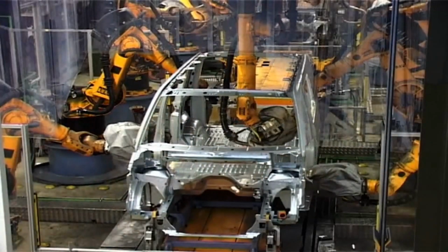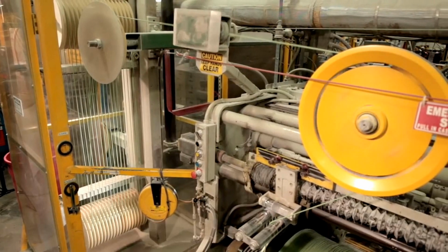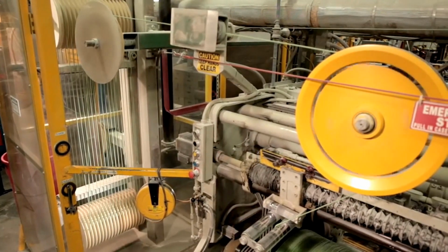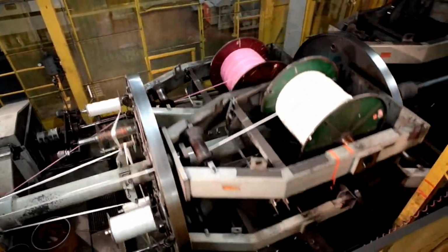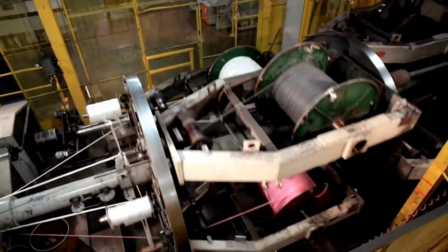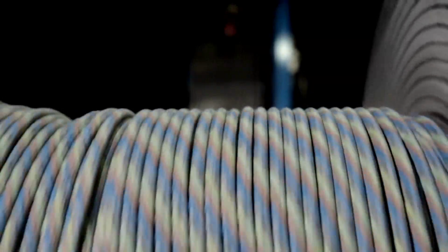In the case of portable cord, which is used wherever temporary power is needed, like on construction sites, in manufacturing facilities, or at entertainment venues, the individual conductors are a smaller gauge, which means bigger in physical size. The insulated conductor is taken up on metal reels before moving to the cabling operation. The portable cord conductors are typically black, white, green, and red, but can be produced in other colors. The color depends on the conductor count of the finished product, the country of use, or a customer requirement.